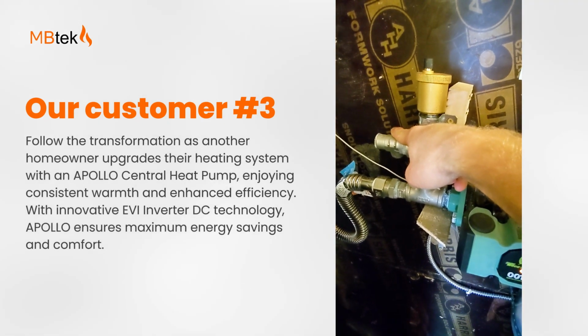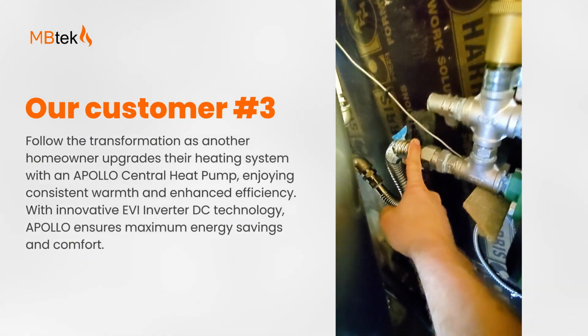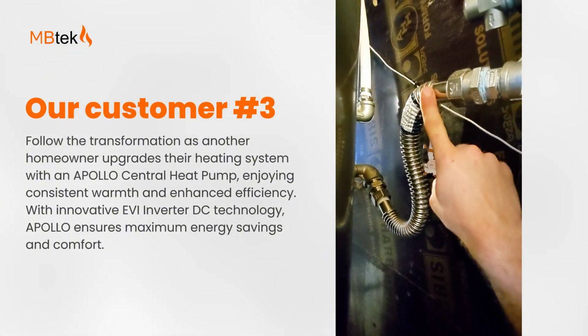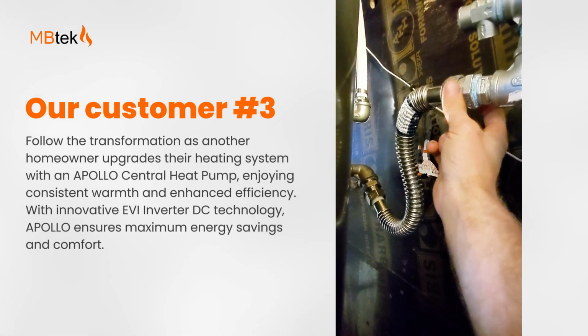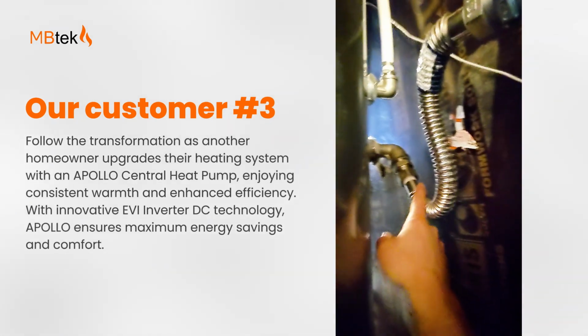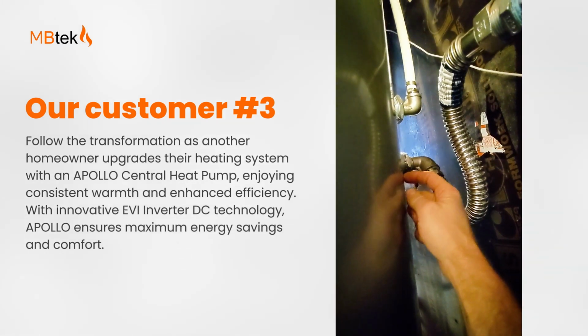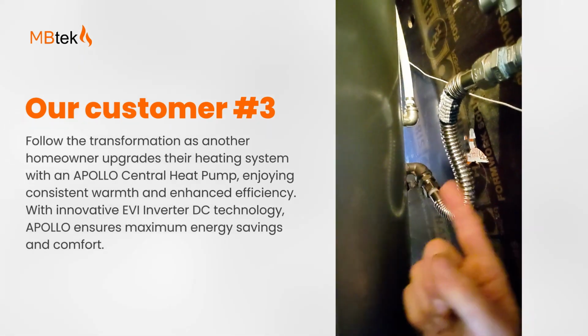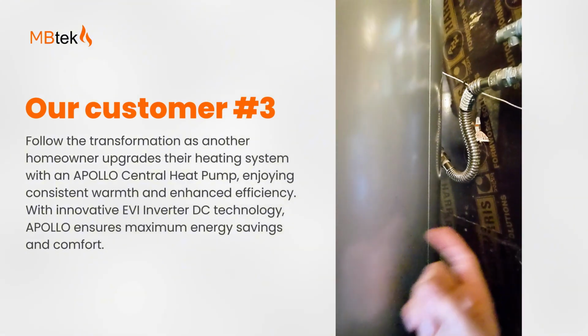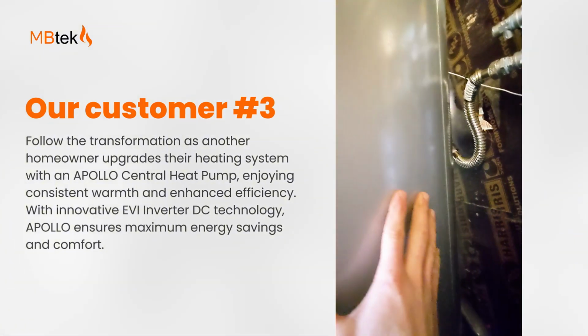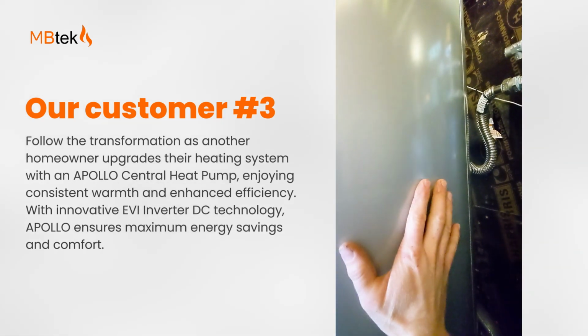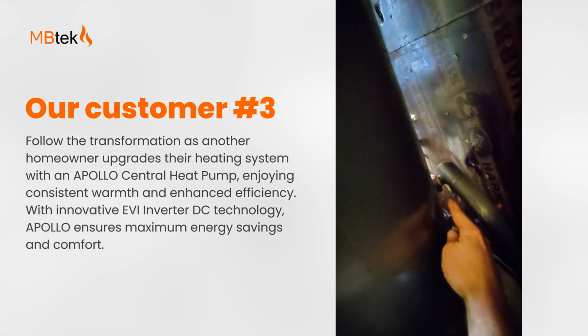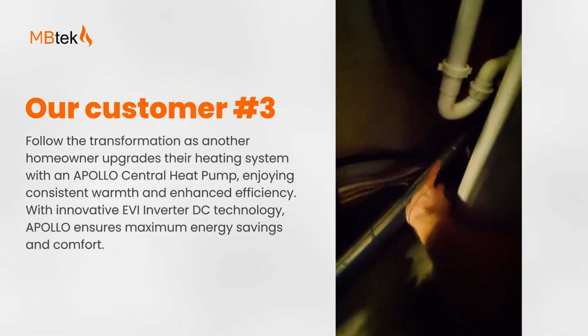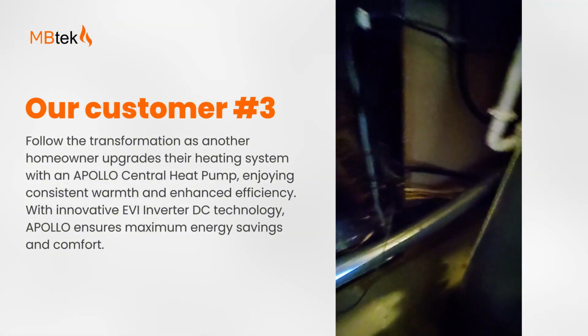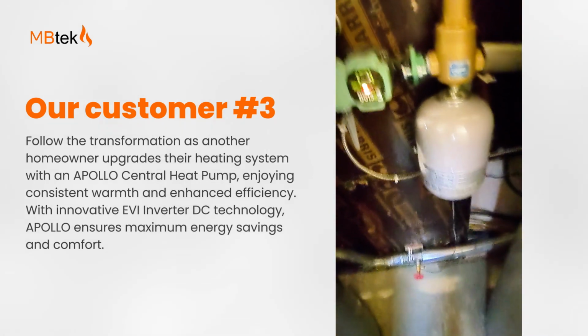Then here a pressure relief valve, and then the water heater connectors, stainless steel that just screwed onto these fittings here and here, and it goes into the buffer tank, into the heat exchanger in the bottom of the tank, where the fluid gets circulated, moves through those coils, gives off its heat onto the 130 gallons of water in the tank, comes back out the bottom here, 10 degrees Fahrenheit colder, and then I have a drain valve, and then this 1-inch PEX pipe goes back out to the heat pump, where the whole cycle starts again.